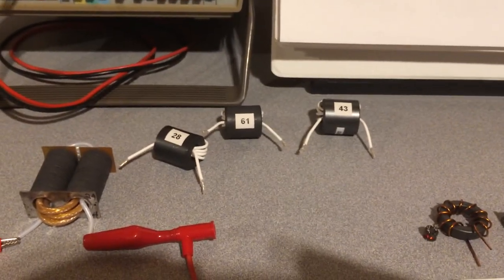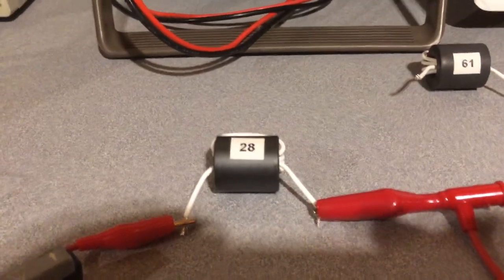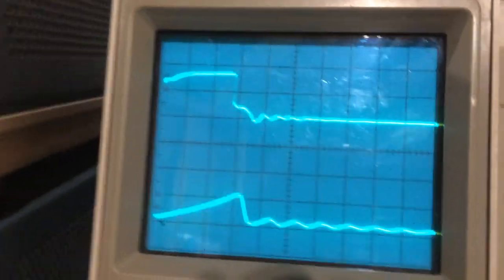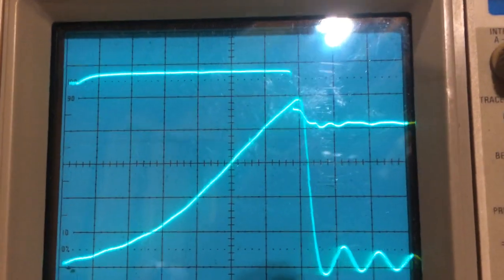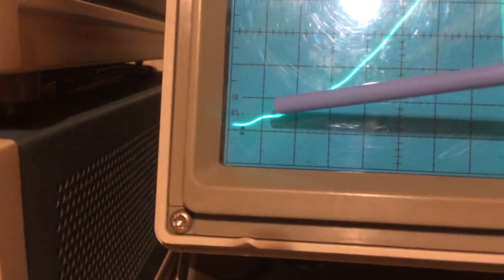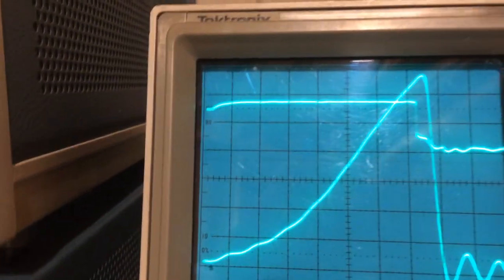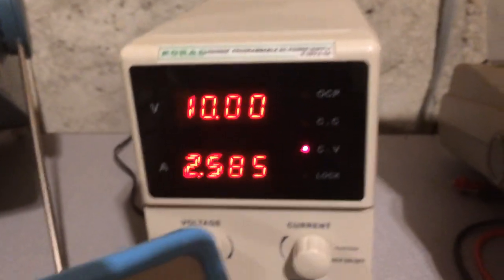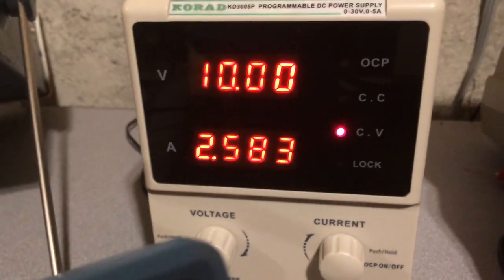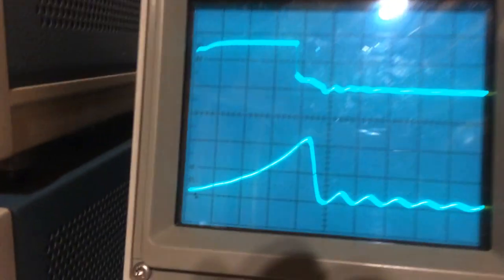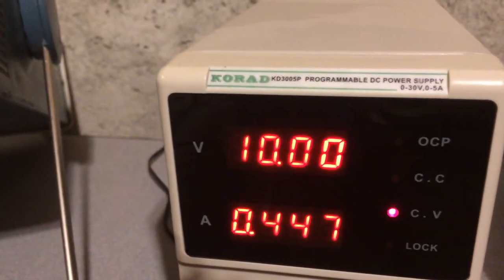Now let's look at material 28. The waveform starts and seems fairly linear, but as we increase it you see immediately that instead of a straight line we have a curve — it's nonlinear. At about 2.5 amps DC it's clearly nonlinear, and looking more closely it appears to become nonlinear closer to about half an amp DC, with maybe 5 amps peak.